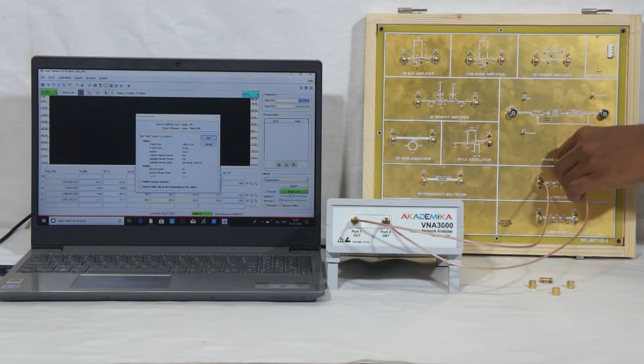Set the start frequency to 1 MHz and stop frequency to 1 GHz. Run single scan. The display window will show the transmission coefficient S21 of the lumped LPF. Insert markers as shown and measure the 3 dB cutoff frequency of lumped LPF, which is seen at 425 MHz. Now, select the reflection mode in the software. Run the single scan. The display window will show the S11 return loss of the device under test.